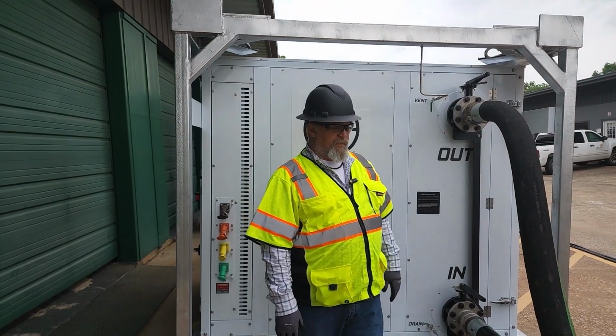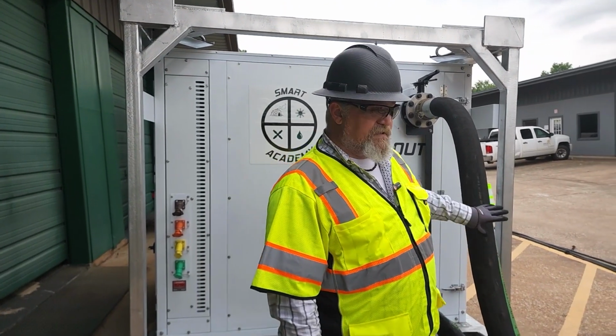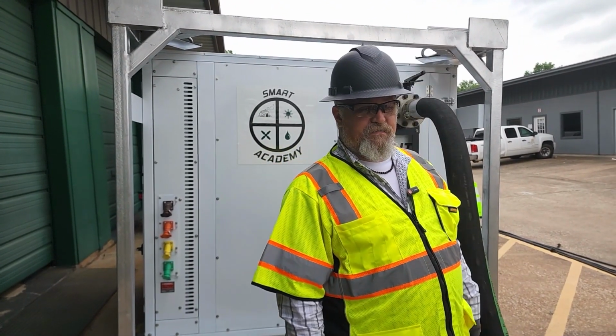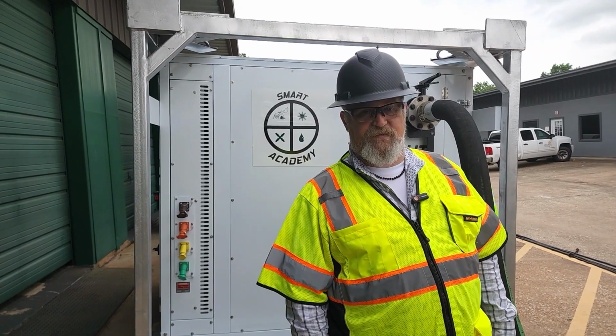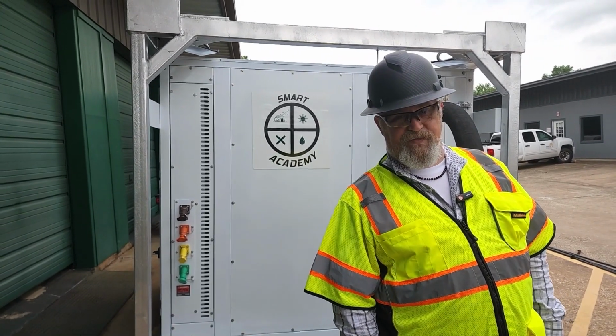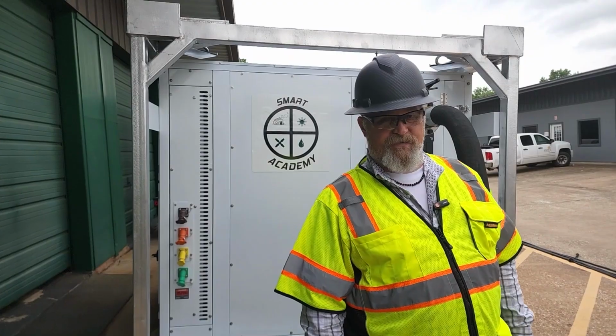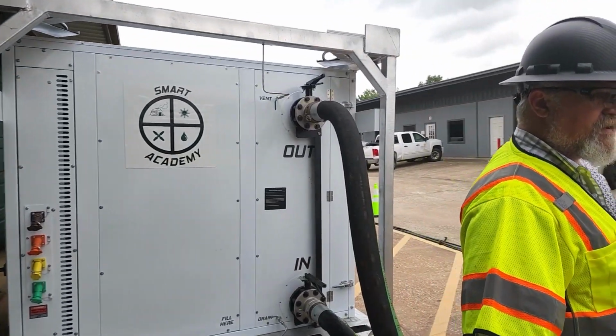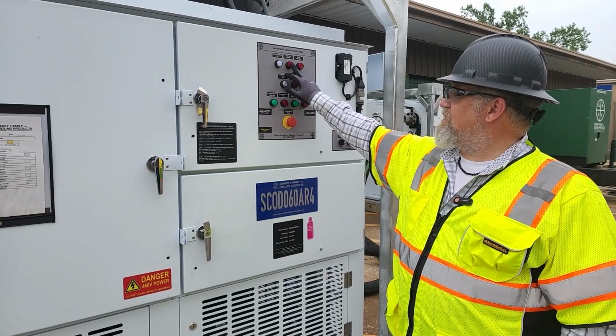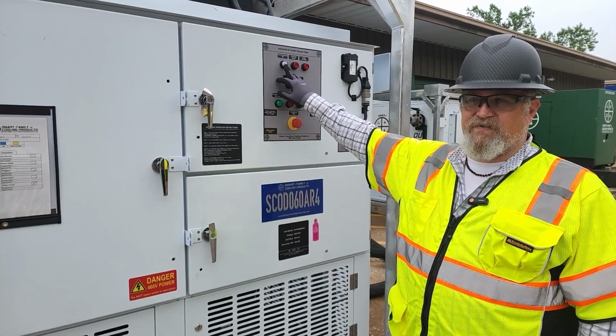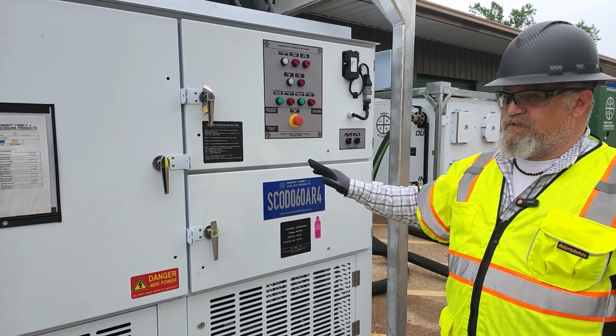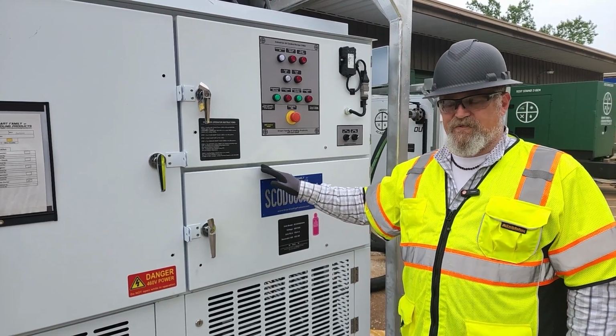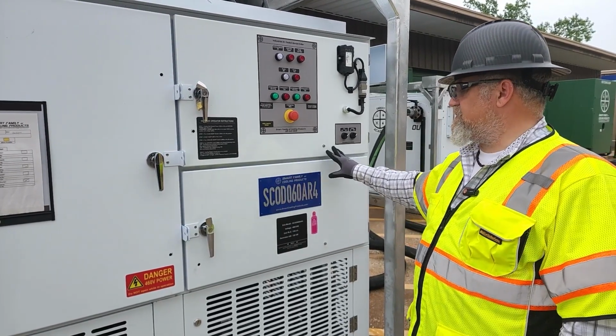Okay, so I suspect that there's air still trapped in this system. So what I'm going to do is adjust my triple duty valve back down to 25%. And then I'm going to bump the pump. So let's take a look at that real quick. I've turned main power on. My compressor power is turned off. My control power is now on. So I've reduced my triple duty valve to 25%, normal operation for this job.